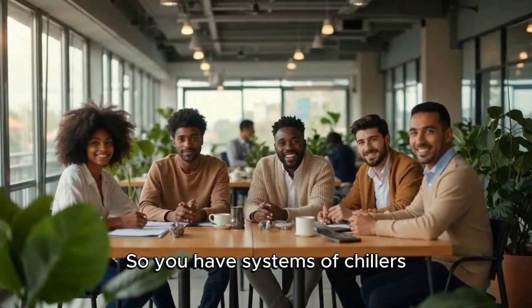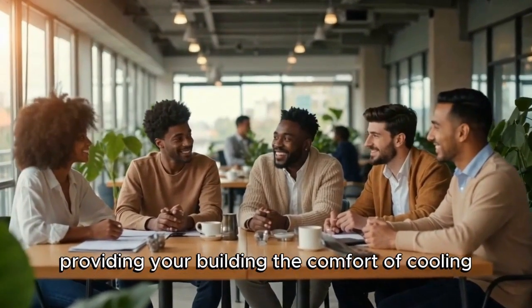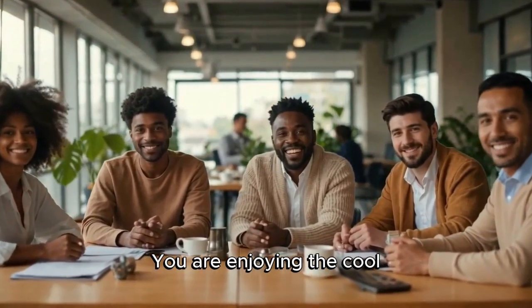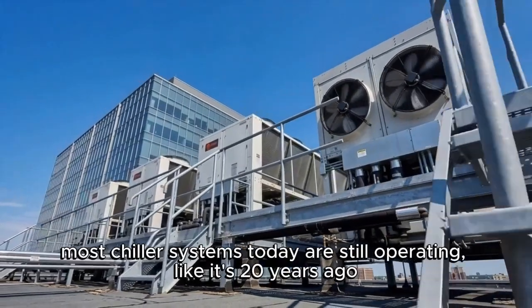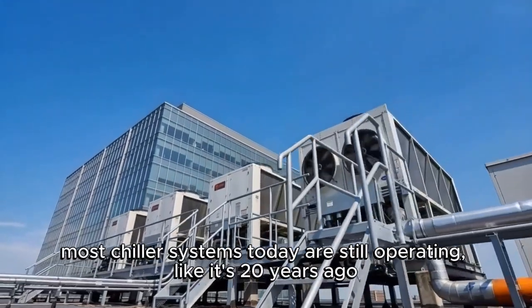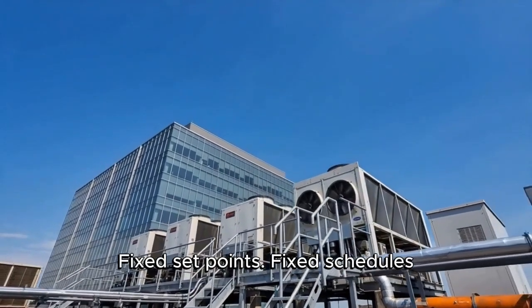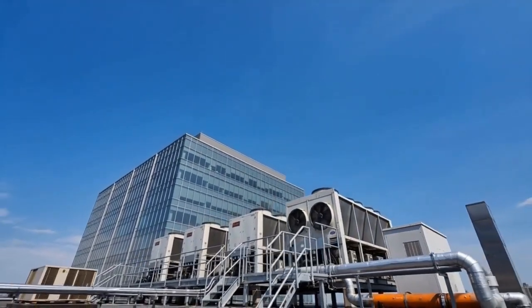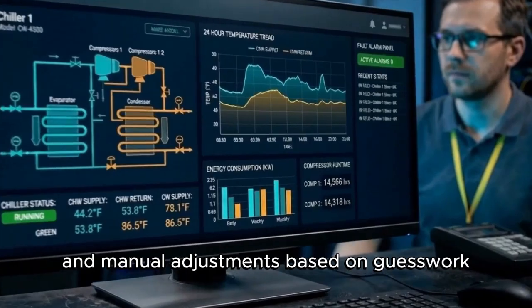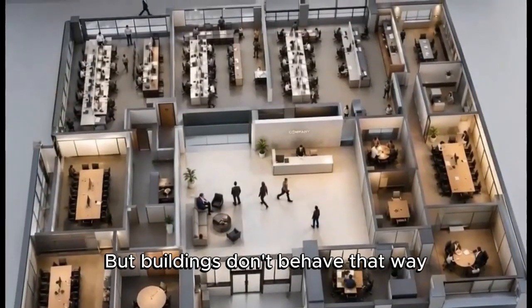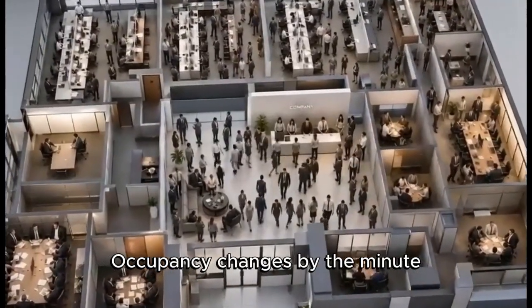So you have systems of chillers providing your building the comfort of cooling. You are enjoying the cool. But did you know that most chiller systems today are still operating like it's 20 years ago? Fixed set points, fixed schedules, and manual adjustments based on guesswork. But buildings don't behave that way. Occupancy changes by the minute.